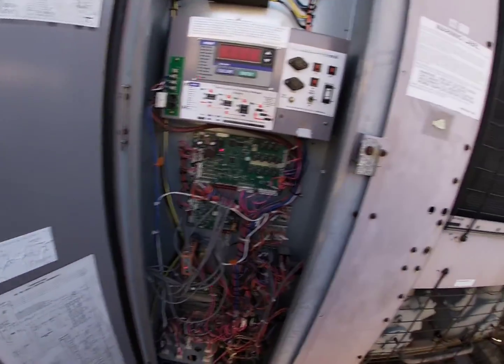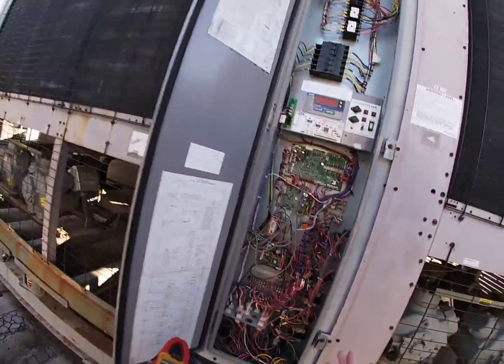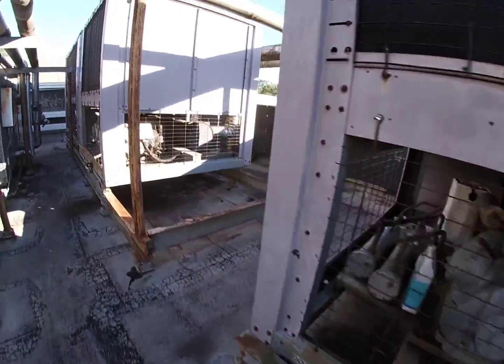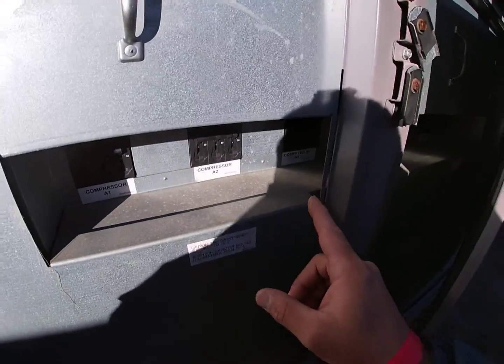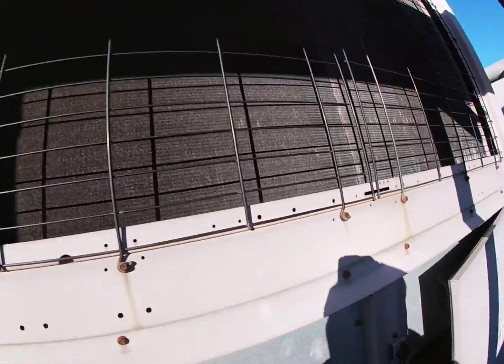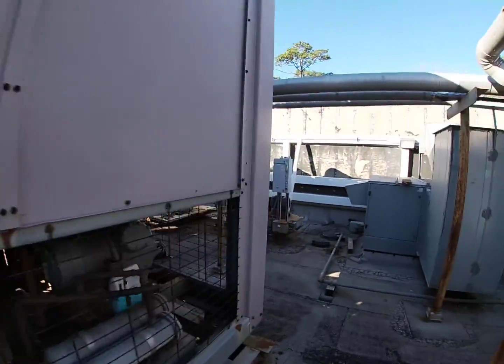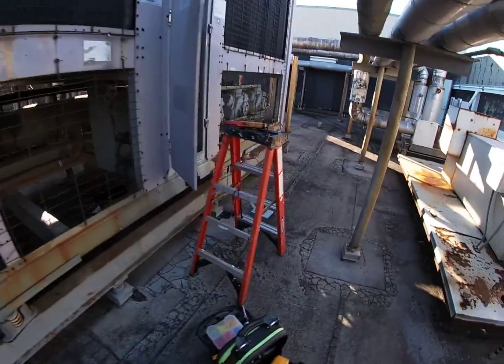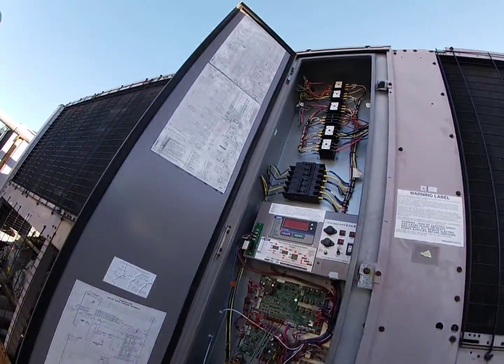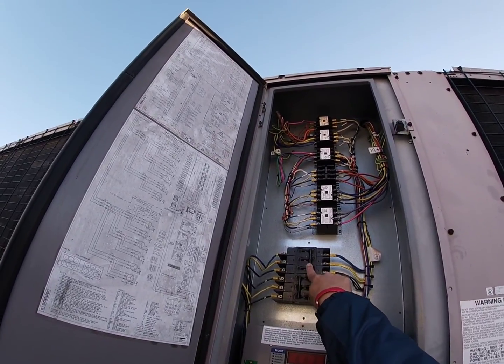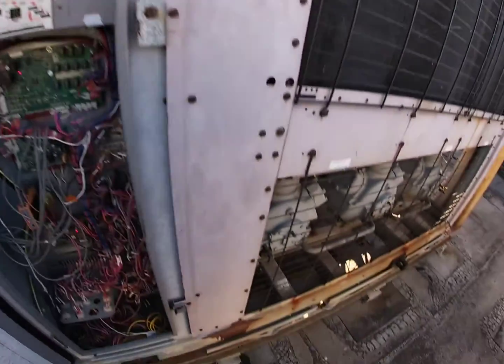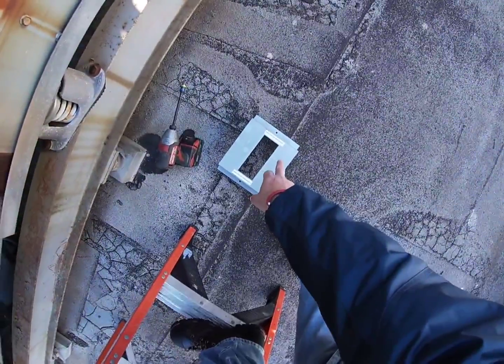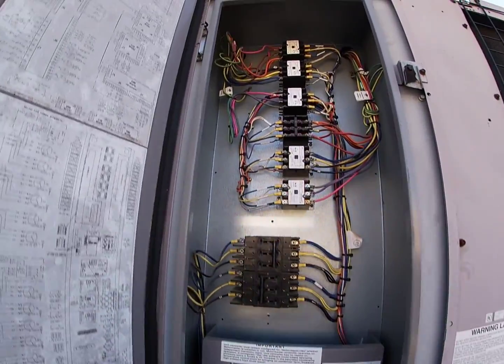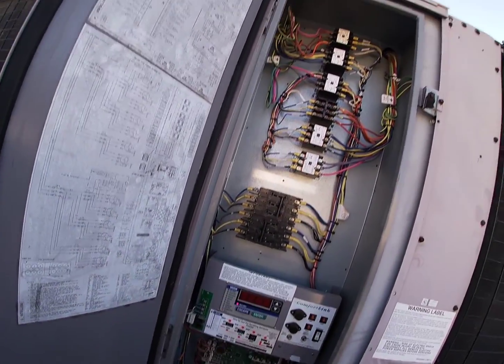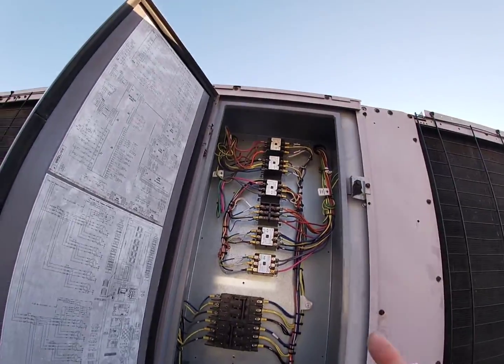So one thing I like to do is I like to look at everything, especially when it's a compressor failure like that. First thing I'm gonna do is go to the compressor breakers here, which I already did, and they're all on here, so none of those are tripped. So the other thing I like to do when I'm looking at this is look at everything in this panel and see if I see anything out of the ordinary, which I did. I saw this for your condenser fan motors trip. I took the panel off, but that was circuit 1, or yeah, circuit 1 for the condenser fan motors.